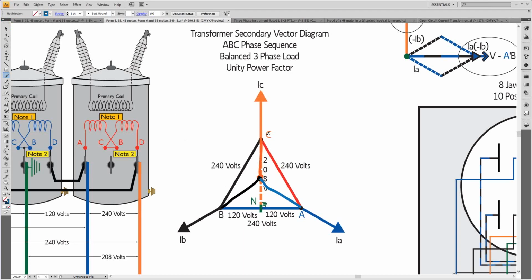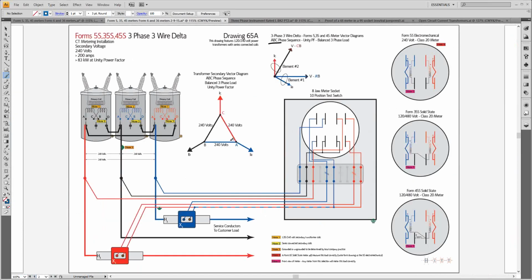as I look at the three currents that are IA, IB, and IC, and see the phase relationship of those three currents, they sit at 120 degrees out of phase with each other. So from IA to IB, it's a 120 degree phase shift. From B to C is 120 degrees, and then C back to IA is 120 degrees. So those three currents, in a balanced three-phase circuit, and we can go back over here for a second just to show you what I mean, whether it's three-phase four-wire delta with a balanced three-phase load, or three-phase three-wire delta with a balanced three-phase load.